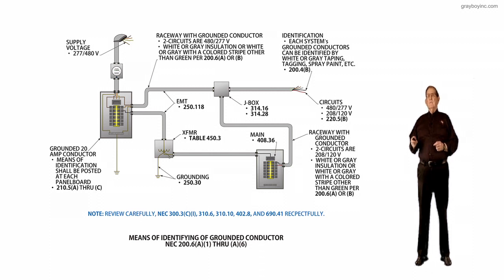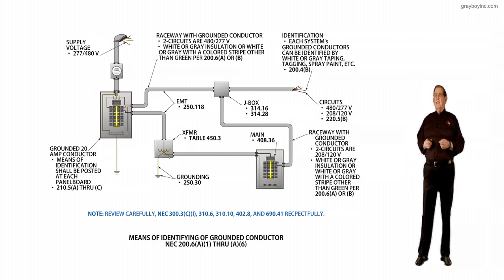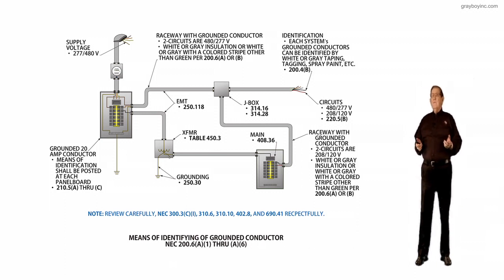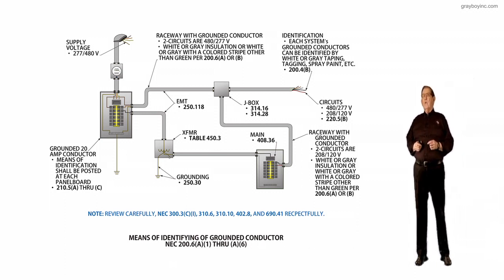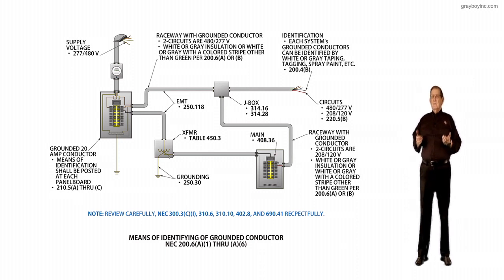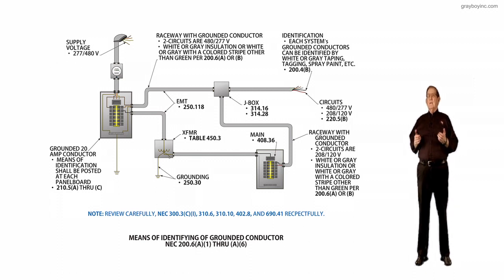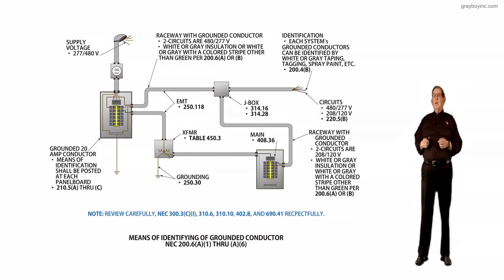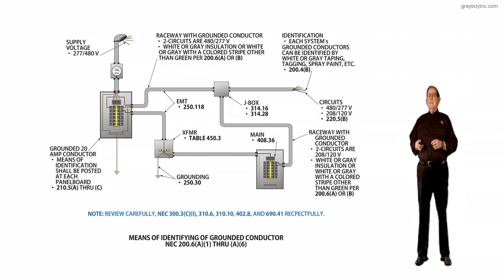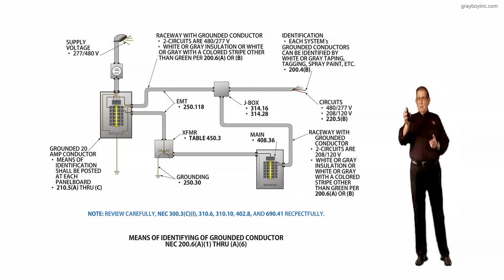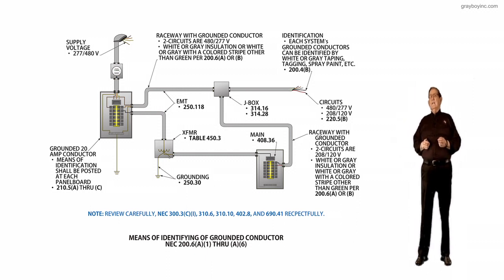First, I would like to look at the conduit coming out of the box that has the title head circuits: 480 volt, 277 volts, 208, 120 volts. 220.5B addresses this where you have 600 volts or 1,000 volts or less in the same conduit system. Secondly, the raceway with the grounded conductor, right below the head I just talked about.